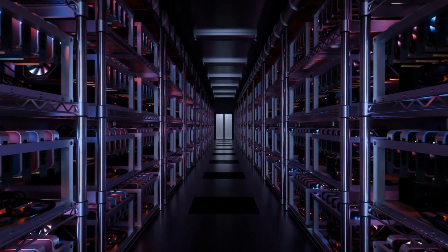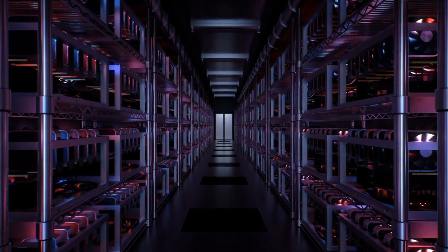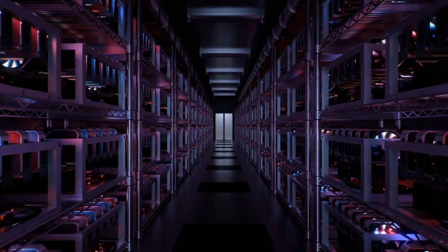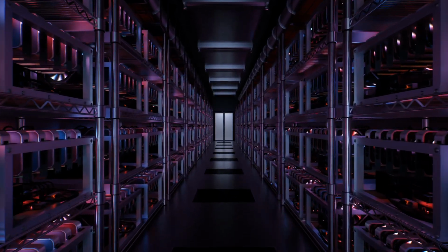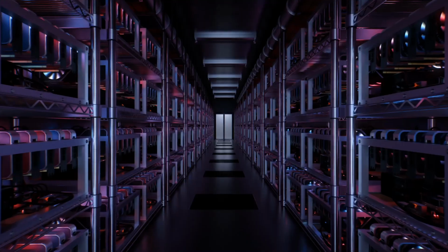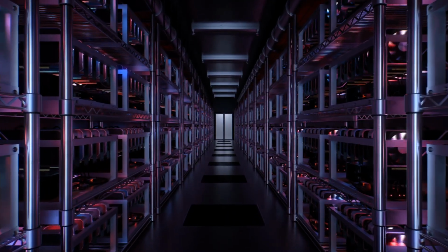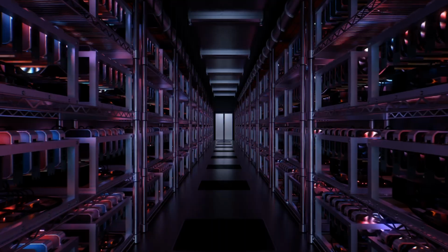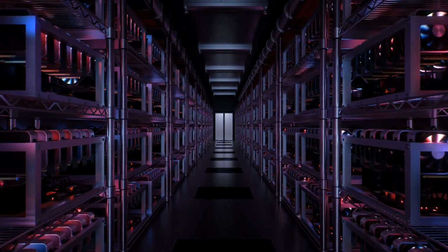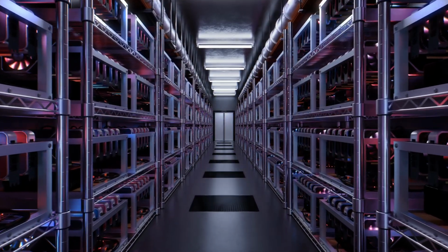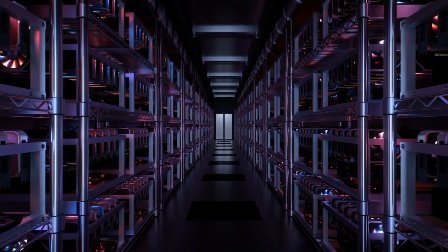So that 18.5 kilowatt power draw is strictly a parasitic load. A parasitic load. Yeah, it is only providing mechanical work. It spins the impellers and the pumps, it powers the sensors, it opens the valves, and it runs the control boards. So you are basically just paying the toll for the transportation network. You're not fighting the heat itself.